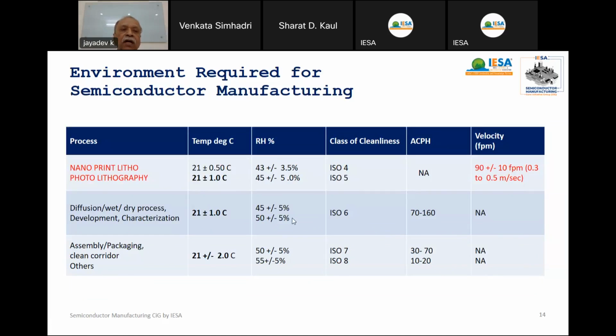So different environments are required for manufacturing in terms of temperature, relative humidity, class of cleanliness, air change per hour, and velocity. For processes like nanoimprint litho, here you see the tolerance is plus or minus 0.5 degrees centigrade. Very difficult to achieve unless proper design is done, proper layout is done. And relative humidity is normally 43 plus or minus 3.5 percent. ISO 4 is class 10 clean room.